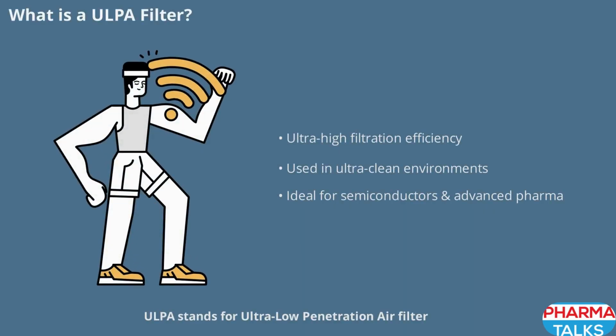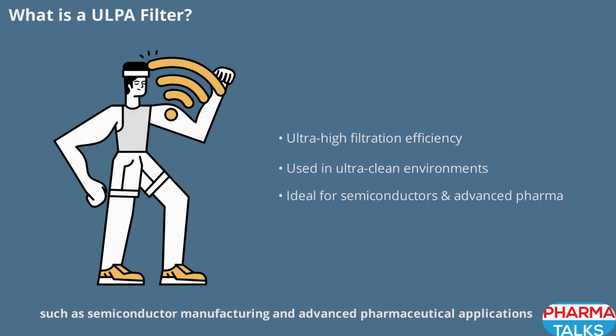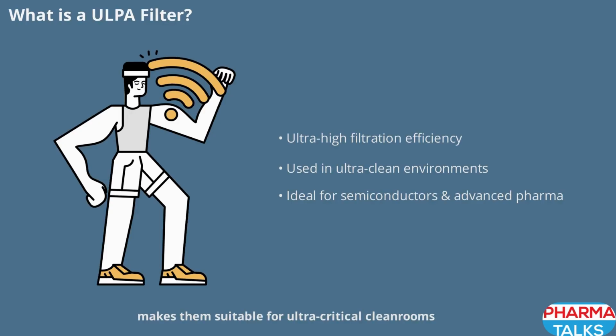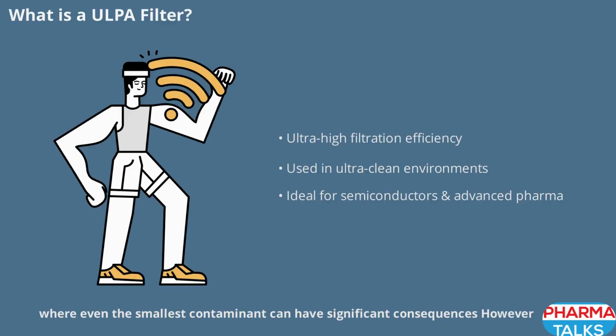ULPA stands for Ultra-Low Penetration Air Filter. These filters take air cleanliness to the next level, offering even higher filtration efficiency than HEPA filters. ULPA filters are essential in environments where extremely low particle levels are required, such as semiconductor manufacturing and advanced pharmaceutical applications. Their ability to capture ultrafine particles makes them suitable for ultracritical cleanrooms, where even the smallest contaminant can have significant consequences. However, this higher efficiency comes with its own set of challenges, which we'll discuss in upcoming scenes.